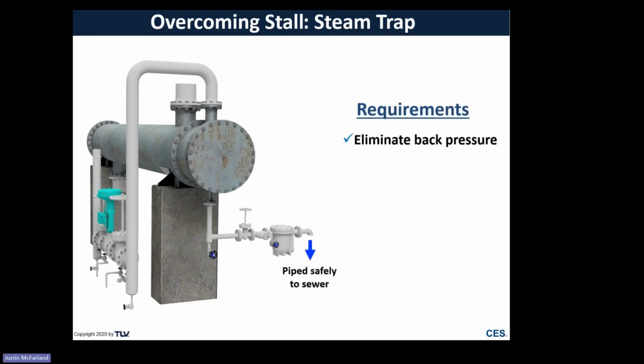If we can discharge that to sewer, well then great. That might help to overcome stall. Now, of course, that's maybe not an ultimate goal. Maybe, depending on the state that you're in or your local jurisdiction, you might not be able to do that. Or if it's an indoor facility that doesn't have a drain nearby, then you might not be able to drain condensate to the sewer. And you might be stuck with problems. But if this is something that you can do, well, then this is an option.